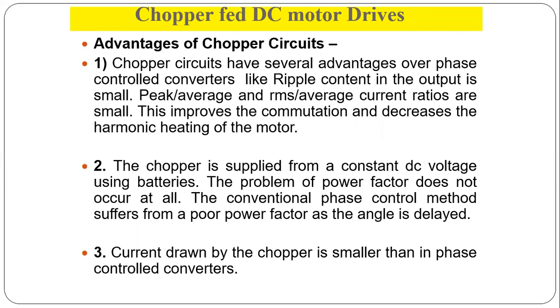Chopper circuits have several advantages over phase-control converters. First, the ripple content in the output is very small, and the peak-to-average and RMS-to-average current ratios are small. This improves commutation and decreases the harmonic heating of the motor, which is one of the most significant advantages of the chopper.